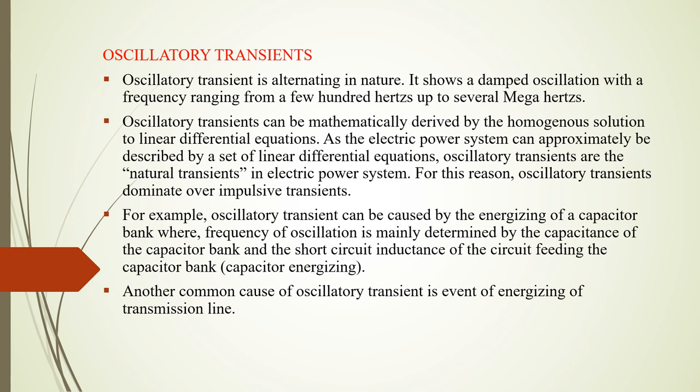What is an oscillatory transient? An oscillatory transient is a composite of a large number of frequency waves that can be of either polarity — positive or negative. The best example of an oscillatory transient is the energizing of a capacitor, because the frequency of oscillation depends on the value of the capacitance. Another common cause of oscillatory transients is the energizing of a transmission line.